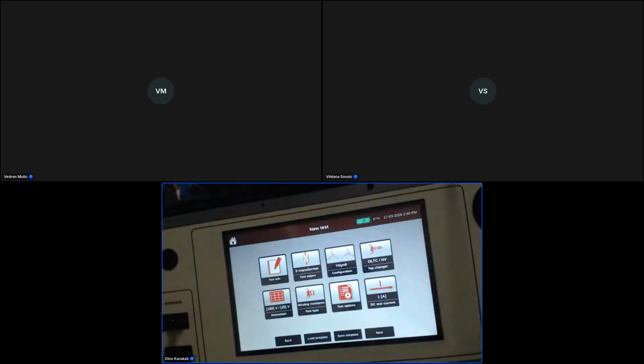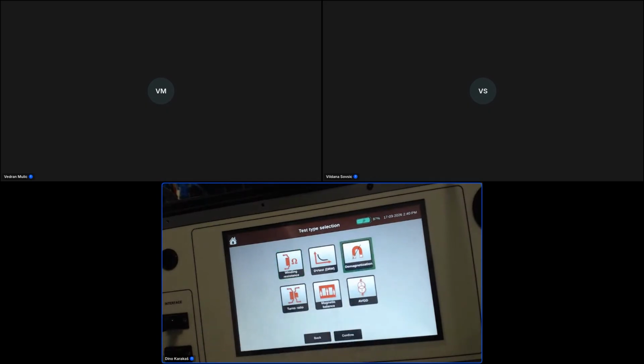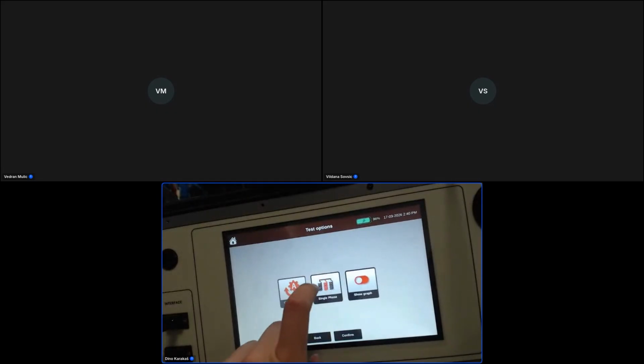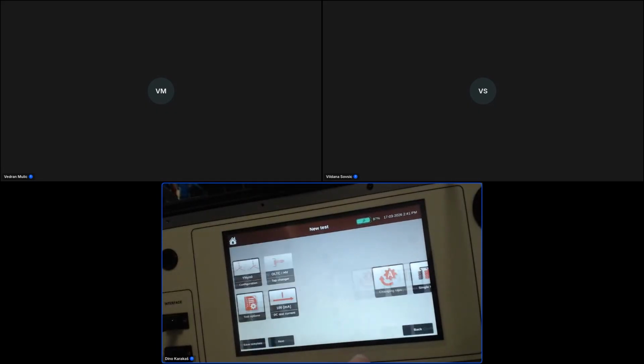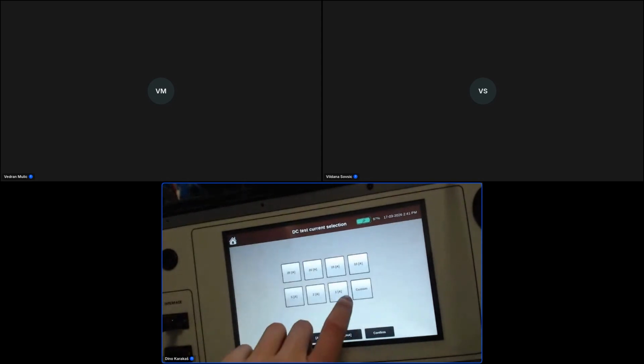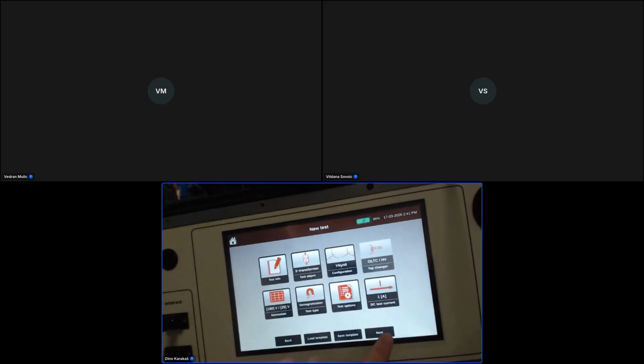And now before we start with the turn ratio test, we will demagnetize the core. So we select the test, which is demagnetization. We press confirm. The test option can be 3-phase or single phase. We will demagnetize only 1 phase, although it's recommendable to do 3-phase, but since I don't want to bother people from Asia, where it's late night, I will go with single phase, select the same test current, press next, and now we wait a little bit.